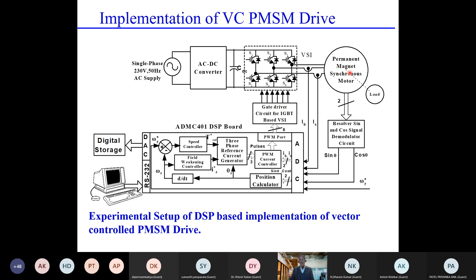Here you see the reference speed, and you are having the resolver signal converted to position and then to speed. So this is the speed controller. From the measured speed, that is the demanded flux, reference flux, or D-axis current, and then you feed into the three-phase reference current generator. This reference current generator feeds into the PWM current controller, which in turn produces the pulses for the IGBTs of this inverter. Then the required variable frequency, variable voltage output is fed into the permanent magnet synchronous motor.